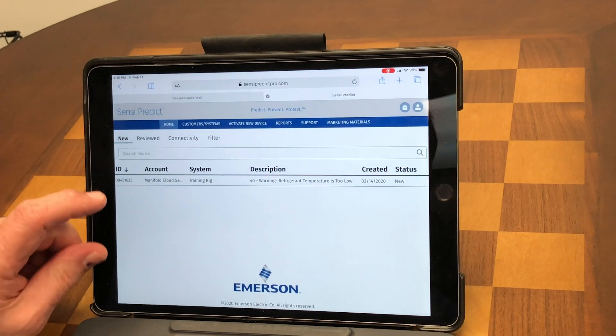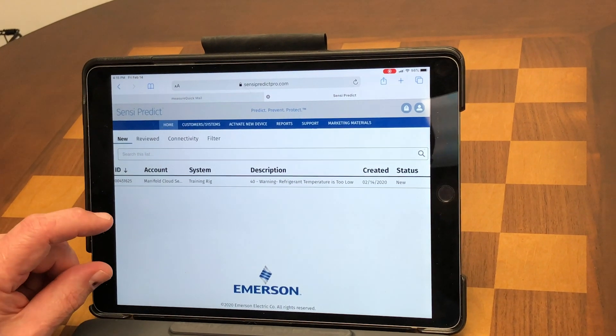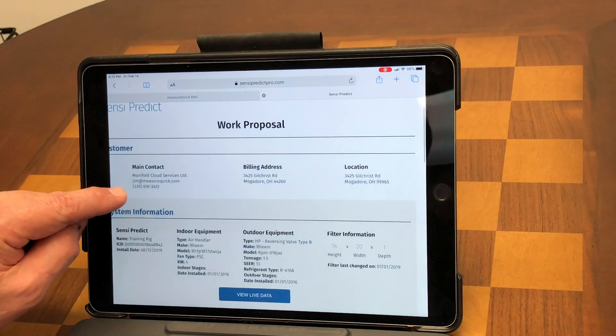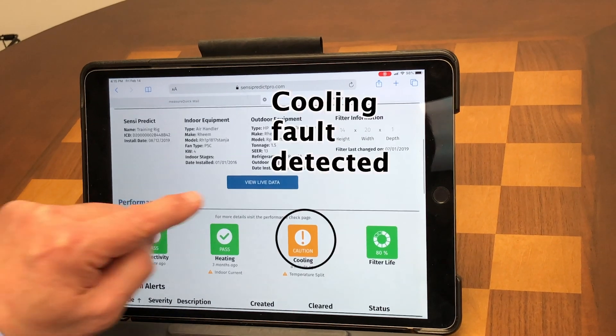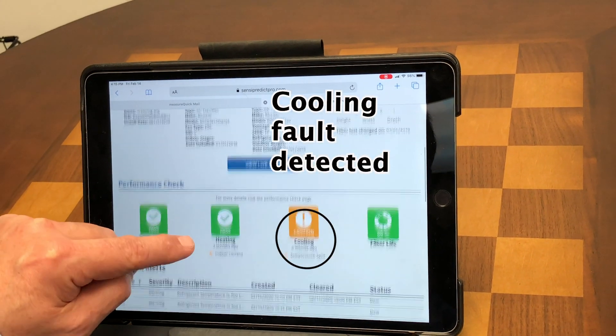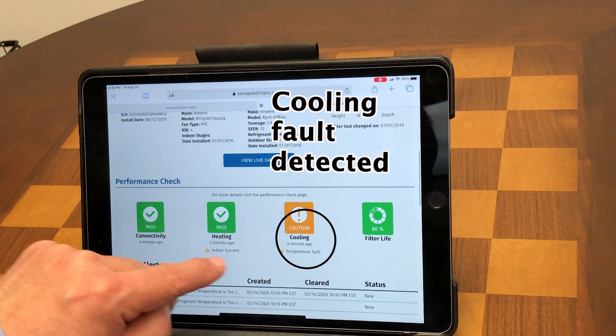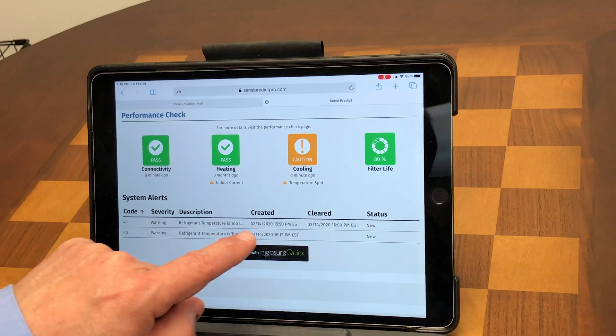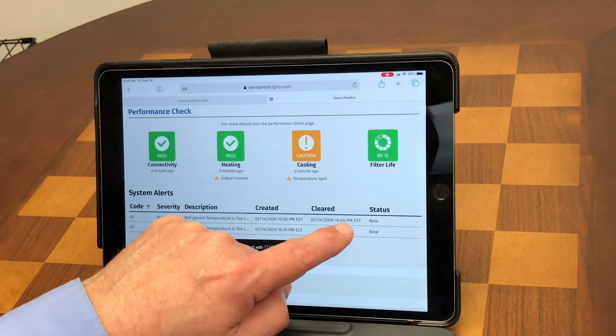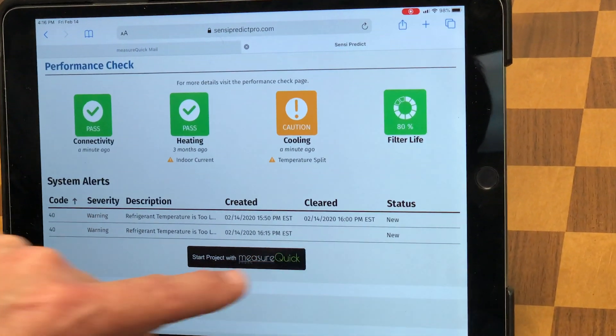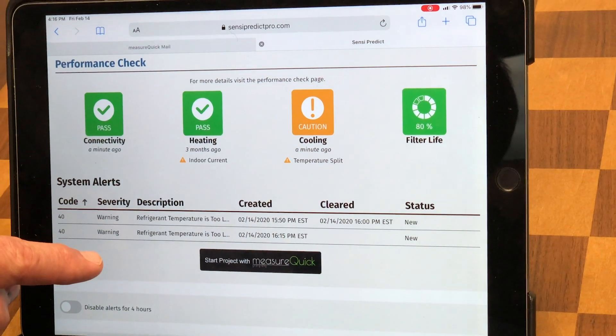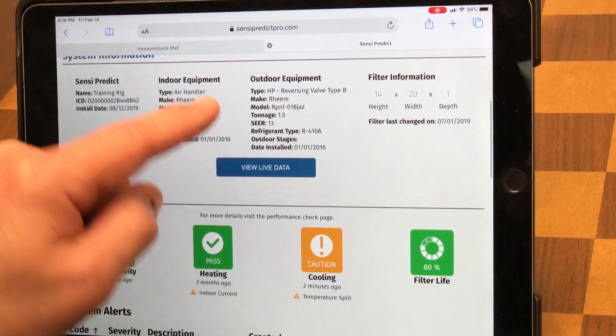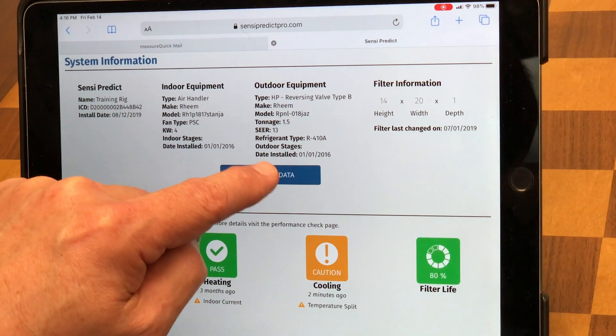If we have a hundred systems there could be a handful of warnings, and eventually those need to be cleared out. All I do is tap on this and it pulls up the information. I can either view live data or I can view it right in MeasureQuick. It's showing me that I have a temperature split issue — at 4 o'clock, 16:00, a warning that the refrigerant temperature was too low.